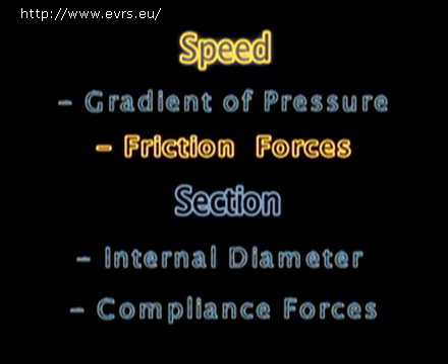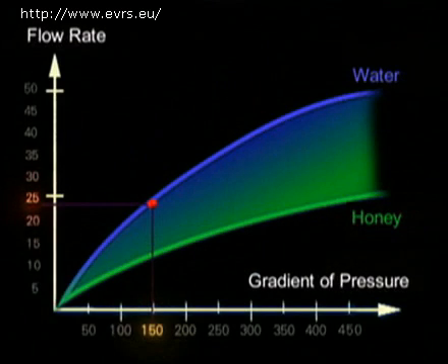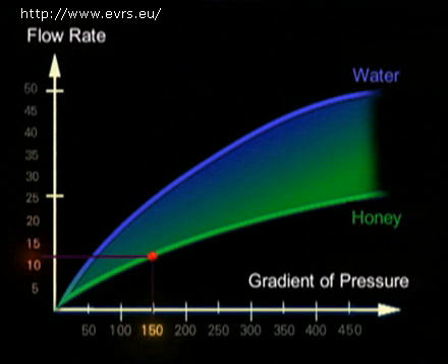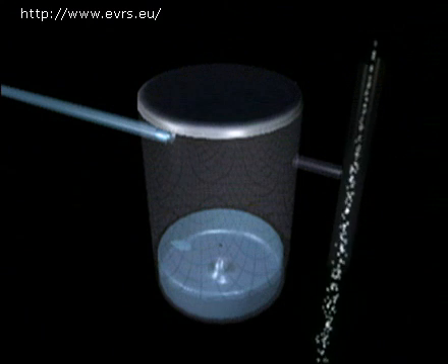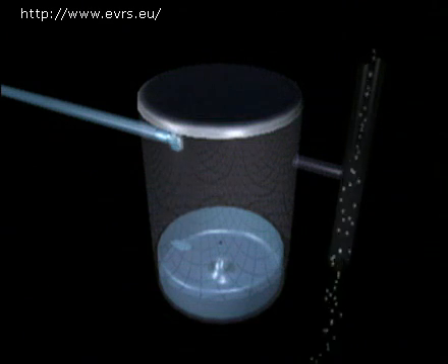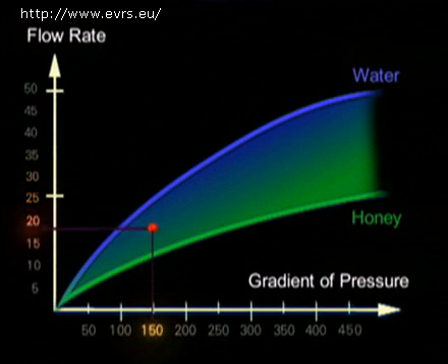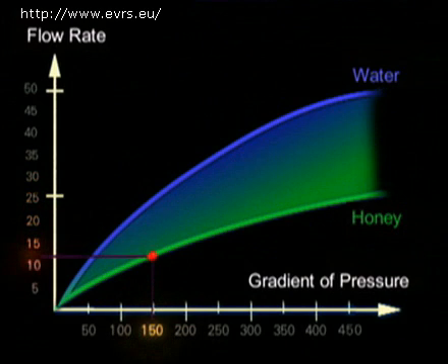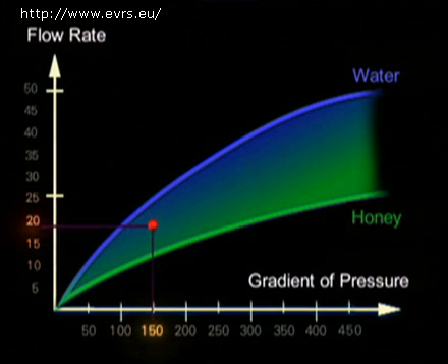The problem is that during a vitrectomy one is not working with a liquid of a given viscosity. This is easily visualized by thinking of honey and water — for a given gradient of pressure, the flow will not be the same in water and in honey. And it is here that we return to the question of which type of pump to use. A pump with vacuum control, like the venturi pump, only allows the operator to control the depression, and therefore the gradient of pressure. One is unable to control the variations caused by the fluid's viscosity, so different flow amounts will result according to the viscosity of the fluid at any given moment.